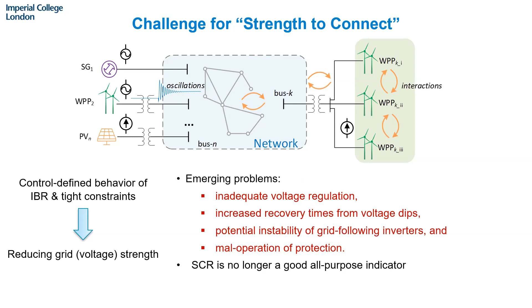The control-defined behavior and the IBR tight constraints have caused a reduction of system strength, and there are several emerging problems that are unique to systems with IBR penetration. We have inadequate voltage regulation, increased recovery time from voltage dips, potential instabilities of grid following inverters, and mal-operation of protection. SCR, in such a case, is no longer a good all-purpose indicator, and we need to define something new. To clarify, our idea is to get a set of new grid strength metrics to address each of the problems individually.